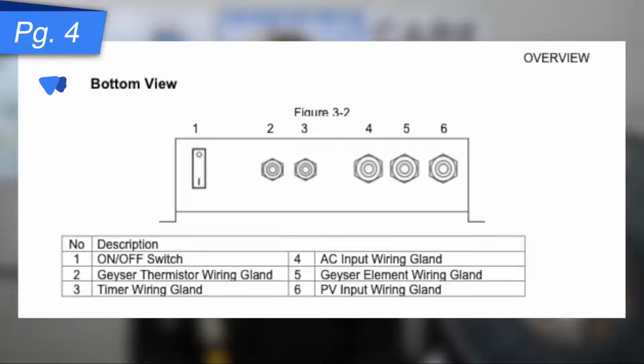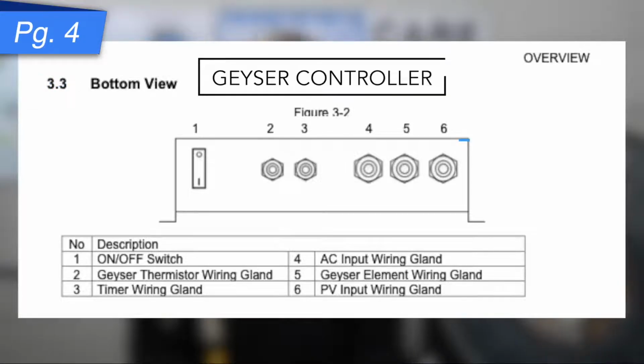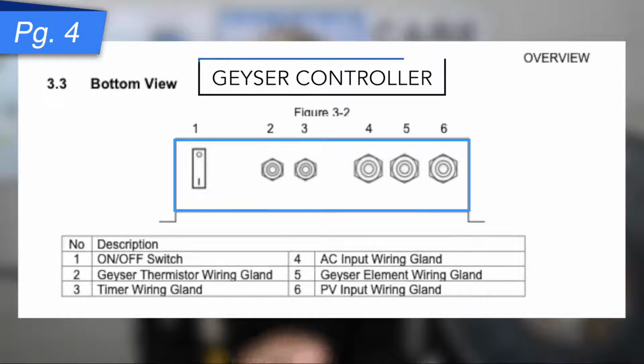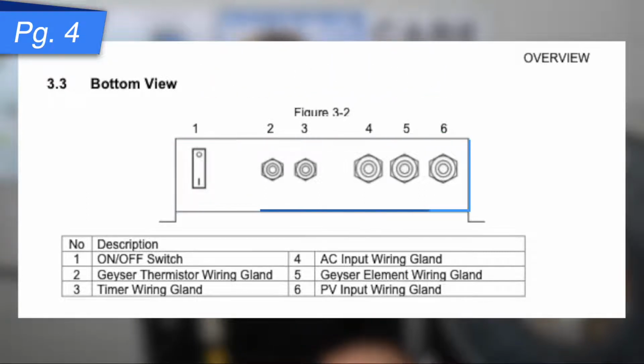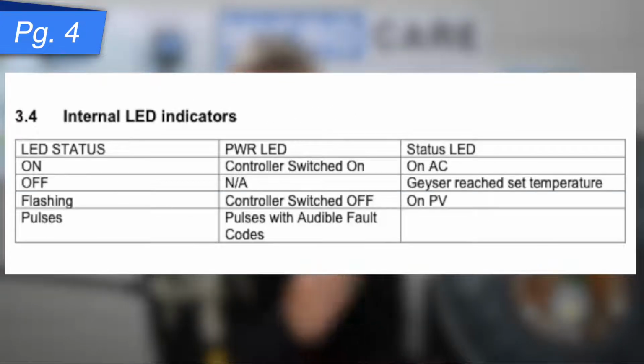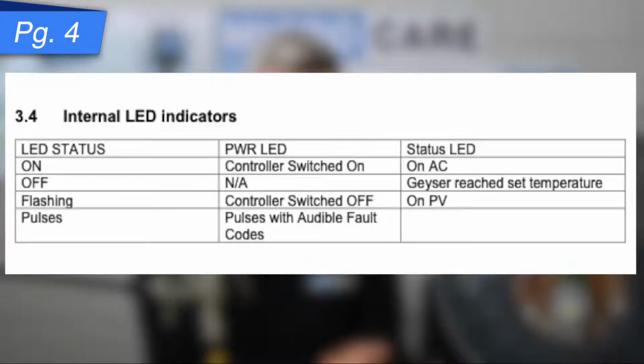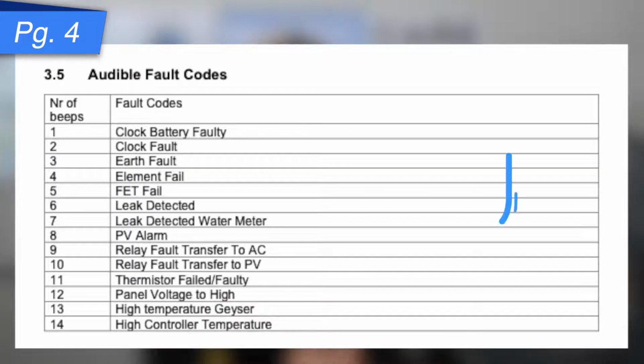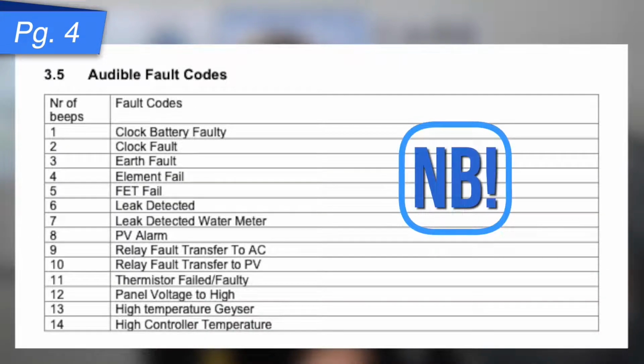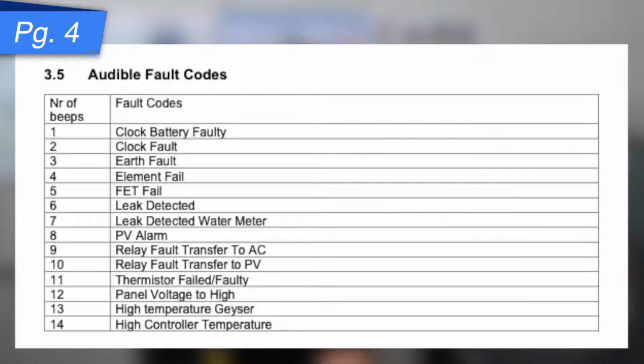Again, we've got a bottom view of the controller and the various glands where we were asking you to put the cables through to connect onto those connector blocks that we saw on page 3. There are internal LED indicators that will showcase various statuses, and those are all available at 3.4. But I want to turn your attention to 3.5. This is going to be really important, that you have access to the Audible fault codes. So what is this? This is the Geyser Controller notifying you if there's a problem.